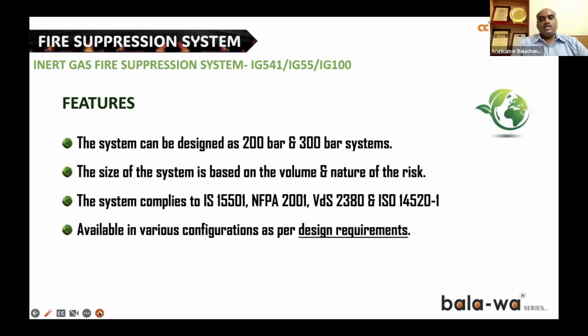The system can be designed in 200 bar and 300 bar. The size of the system is based on the volume and the nature of the risk area. The compliance standard at which the system can be designed is as per Indian standard IS 15501 or NFPA 2001 or VDS 2380 or ISO 14520. Various configurations are available as per the design requirements.